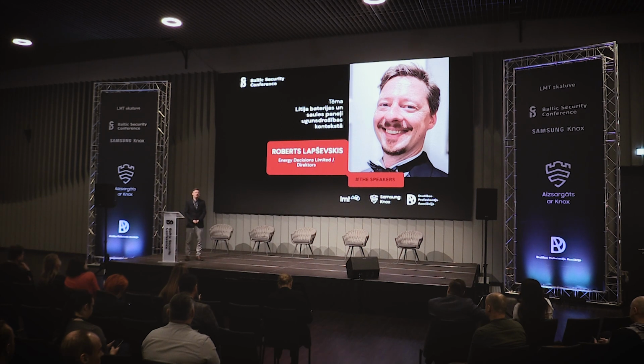I think the most popular document in this area would be the BRE research from 2017, which identified which components would be mostly involved in the fires, and that would be DC components, DC isolators. There's lots of discussion about whether we could get away with not installing DC isolators and instead having equipment with isolators built in, since it's a very large problem, especially from the installer's perspective. Lots of bad workmanship, not using correct ferrules, not using correct cables, not terminating them correctly, getting arc faults.